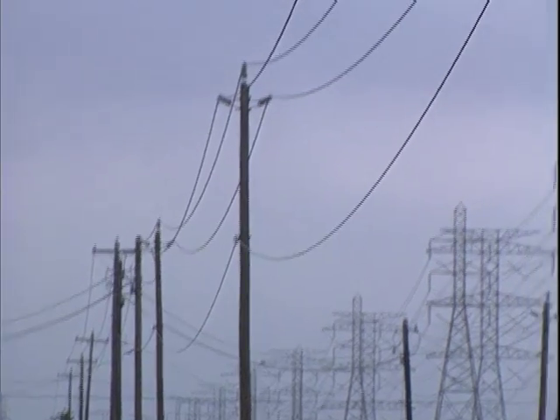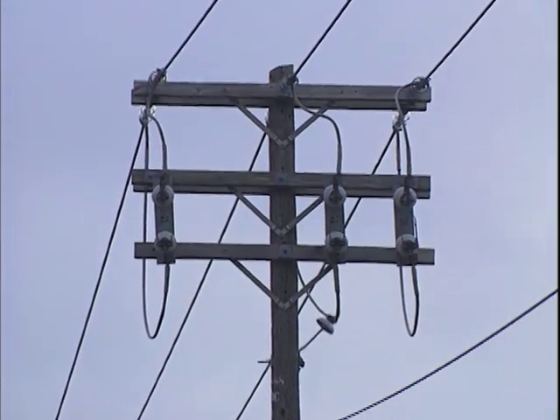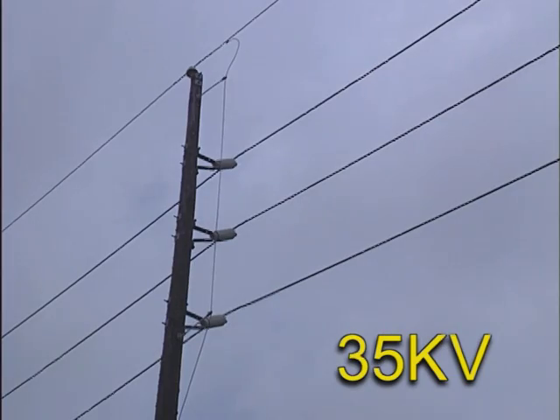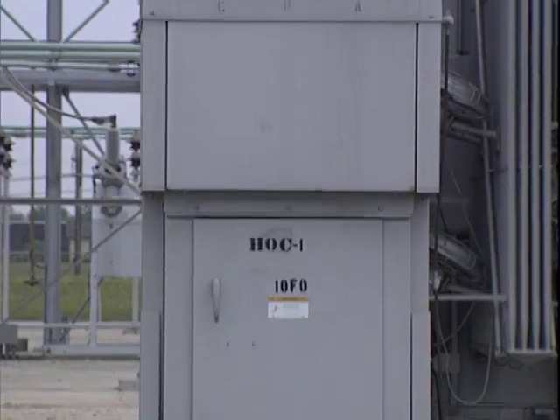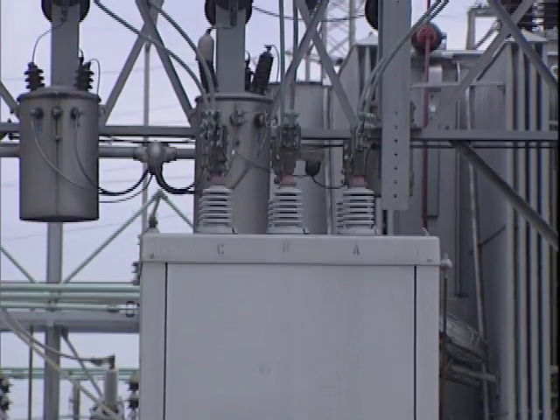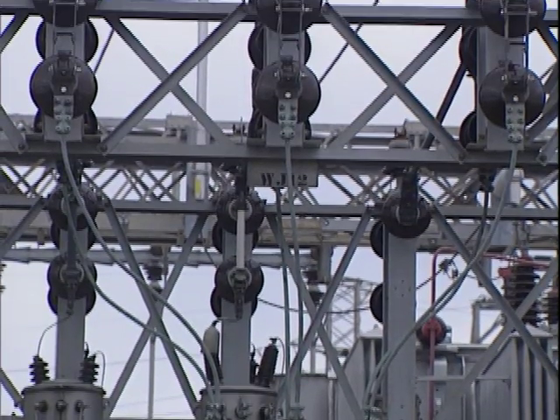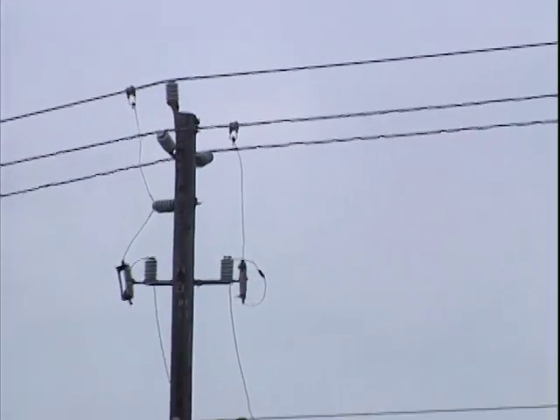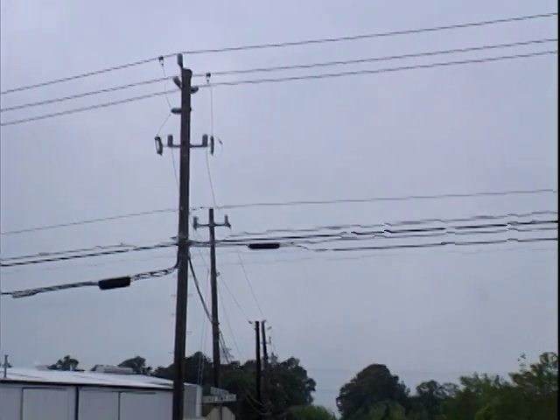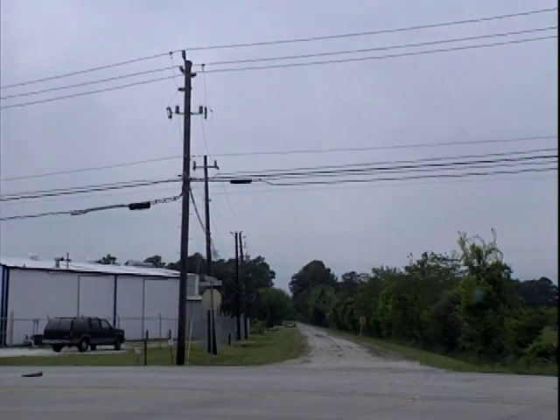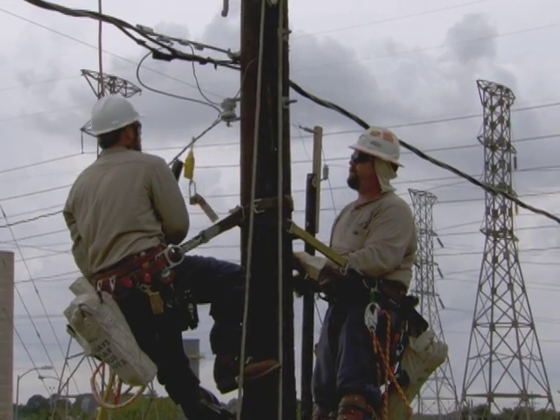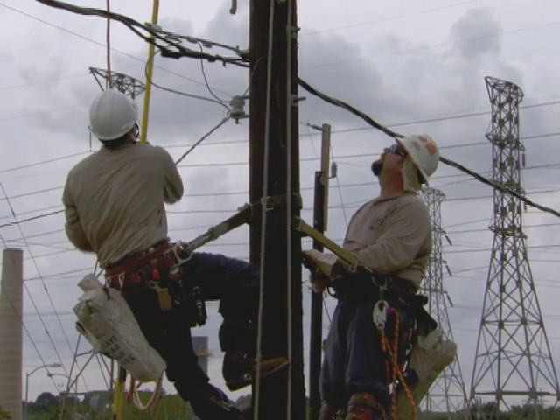Now that you know the basics of our service area and our work policy, here is how work will be assigned and how our system is configured. CenterPoint Energy's distribution system is comprised of 2 primary voltages, 12 kV and 35 kV. Both are connected grounded-wye configuration. Work will be assigned according to circuits or circuit sections. Laterals feeding from circuits will be assigned by laterals. These laterals will be grounded and tagged at the point of feed to designate the presence of a work group.